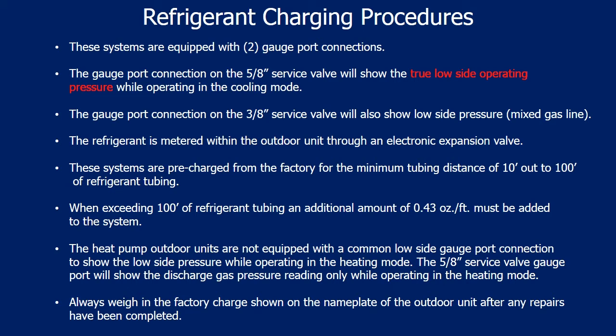The outdoor units are shipped with 2 gauge port fittings. However, the second gauge port attached to the 3/8 service valve will only be used for pressure testing and evacuating the system. This gauge port will not show the true high side pressure when operating in the cooling mode. This is due to the fact that the metering of the refrigerant takes place within the outdoor unit, not the evaporator. These systems are pre-charged from the factory for anywhere from 10 feet of refrigerant tubing all the way out to 100 feet. When exceeding 100 feet, add 0.43 ounces per foot.